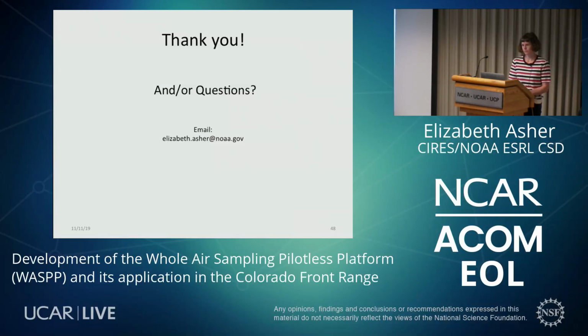Are there more questions? Steve? First of all, Lizzy, thank you for your talk today. Appreciate that. And question on your sample cylinders. Instead of redesigning, have you considered taking an approach like putting a dip tube in? Or maybe a bent dip tube that would give you a swirling inside the cylinder? We hadn't considered that, but we will now. That's a great idea.